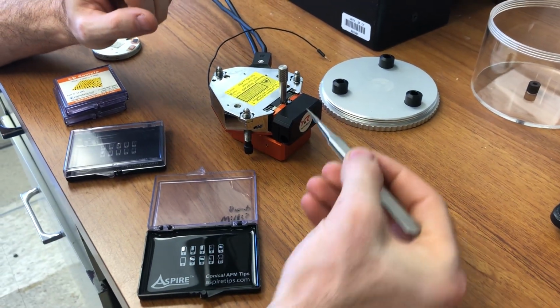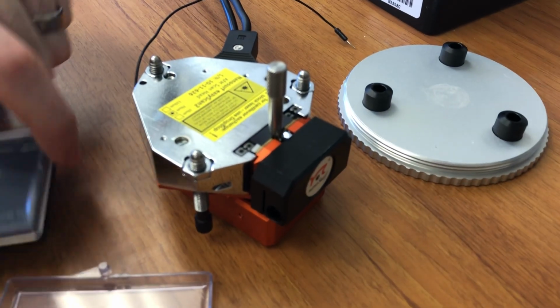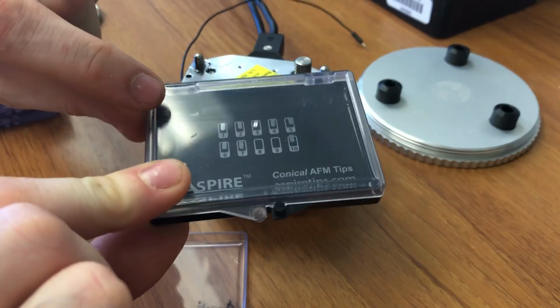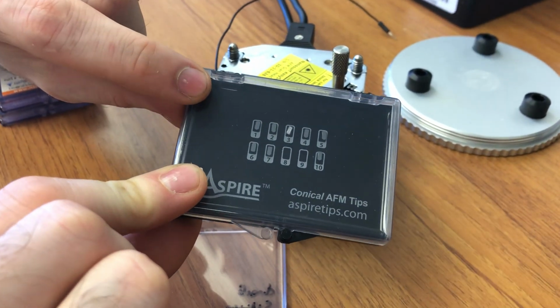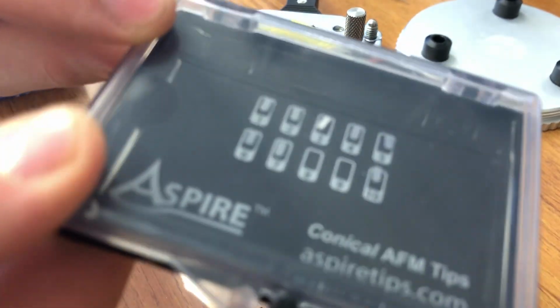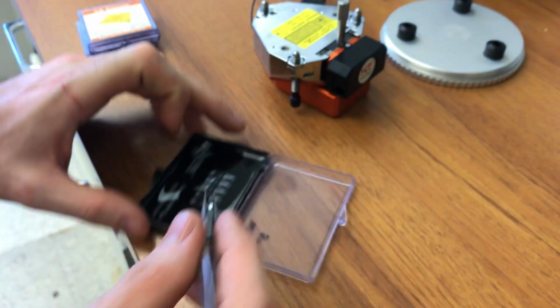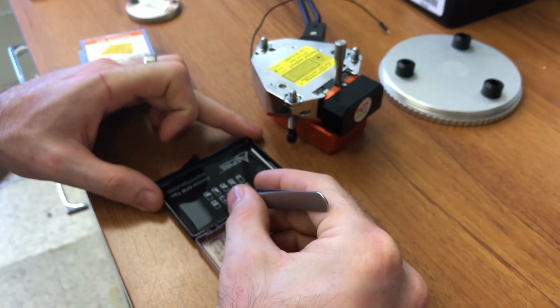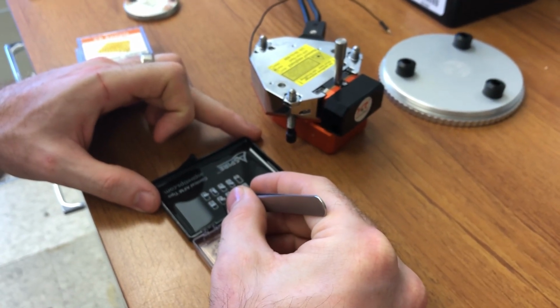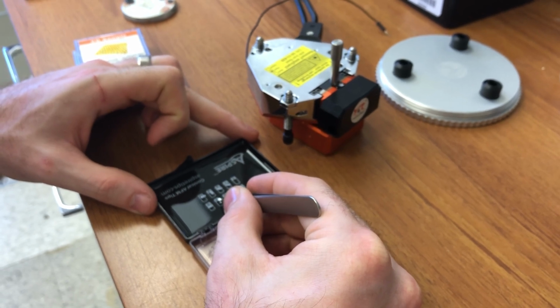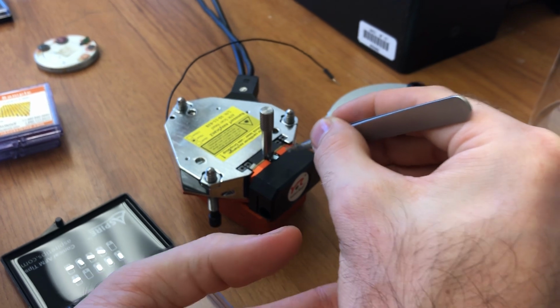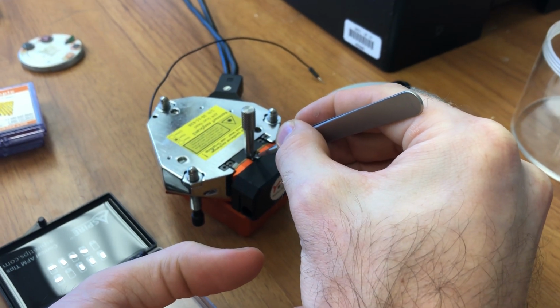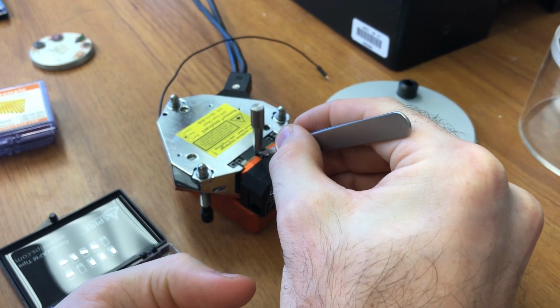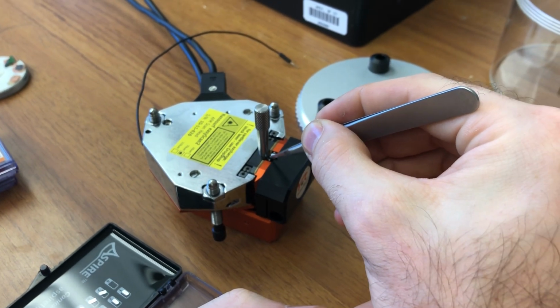Inside there, we've already removed the old tip, but you can see little patterned grooves in that surface. And on the bottom side of these tips, if you see number 3, it also has these little patterned lines in it so that it sits very flat inside there. Okay, we're going to take number 4 from this pack, and we're basically going to put it so that those patterned grooves align with the ones in the holder. So very gently we'll pick this up and put it onto those little patterned grooves, and we'll just give it a little nudge into place.